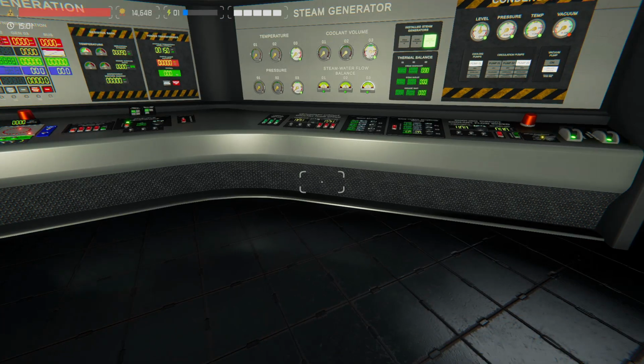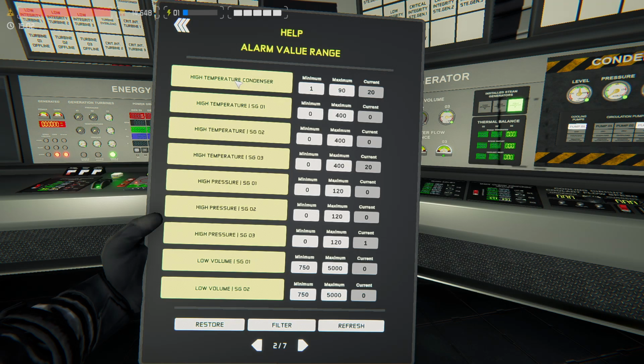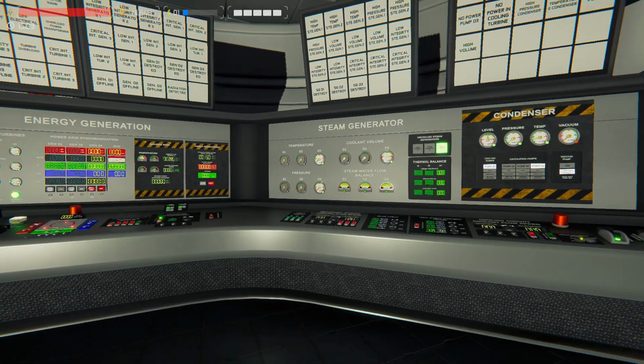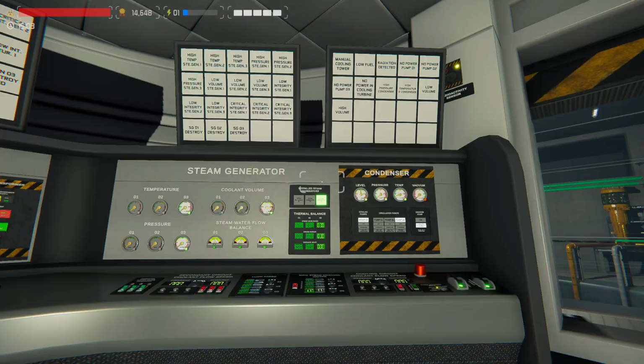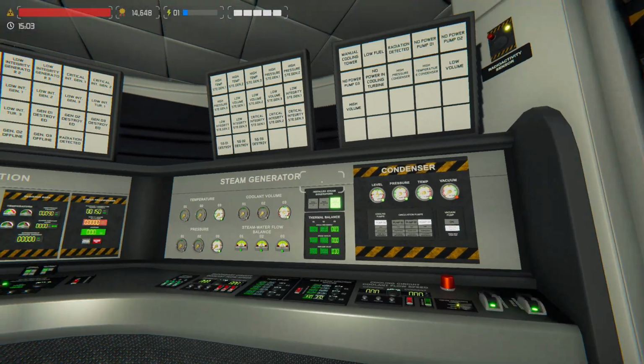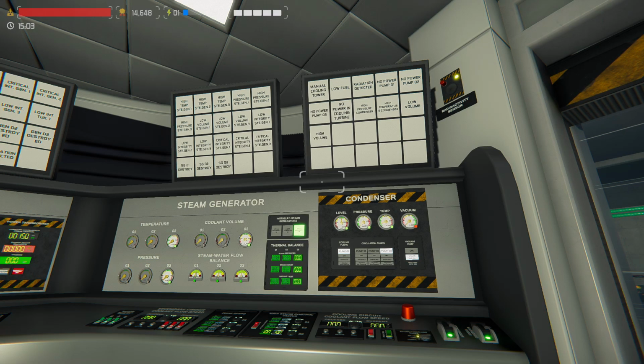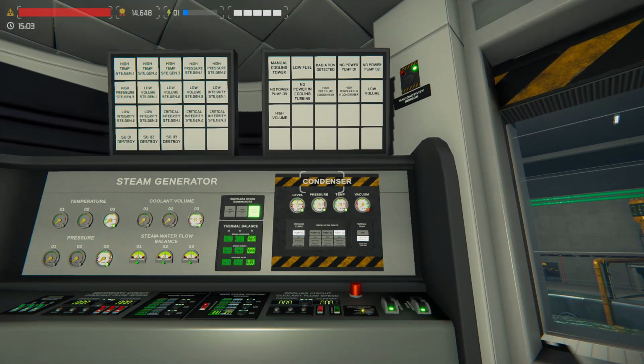So same thing, I set an artificial alarm, page 2, high temperature condenser, I put this at 85. As it rises, I want to get ahead of it. I don't want it to get to 100 - 90 is too close. So if this goes off, like if I'm outside the room or outside the building, I can run back and fix it if I need to.